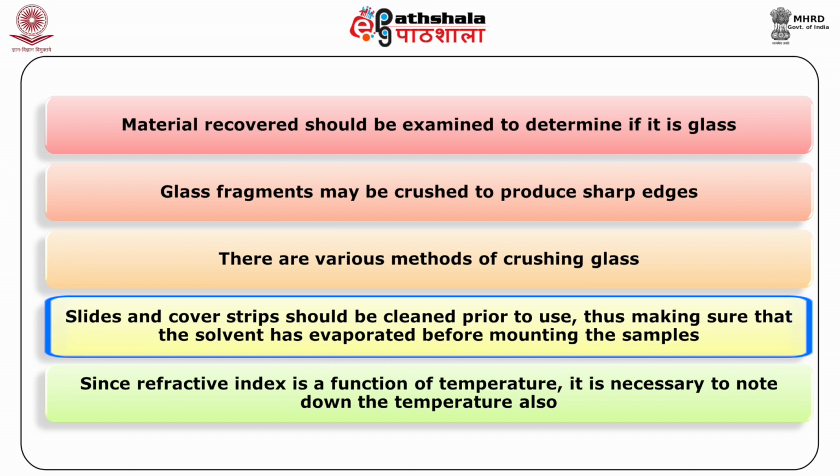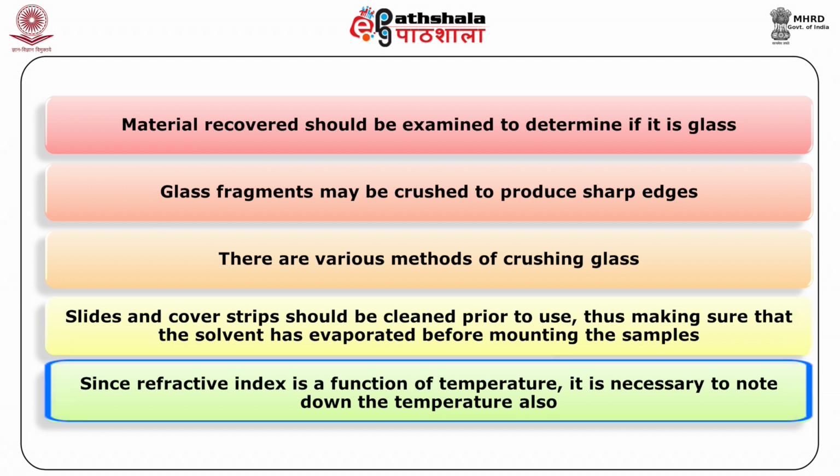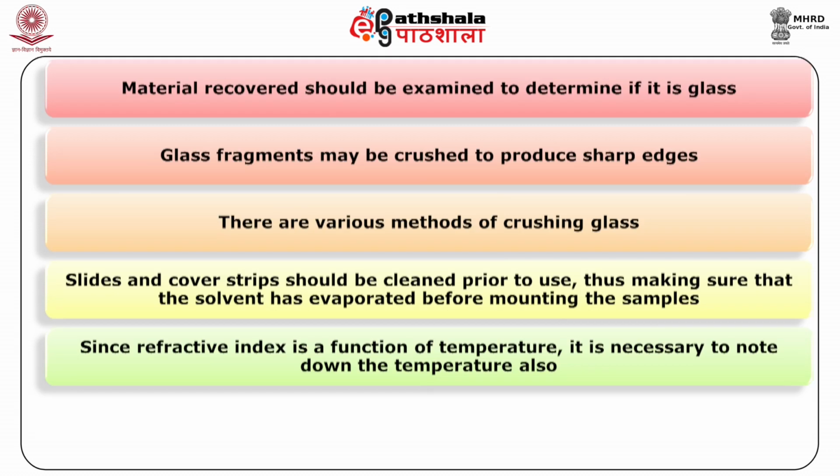Slides and cover strips should be cleaned prior to use with solvents such as acetone, ethanol, or methanol and a lint-free wipe, making sure that the solvent has evaporated before mounting the samples. Since refractive index is a function of temperature, it is necessary to note down the temperature also.